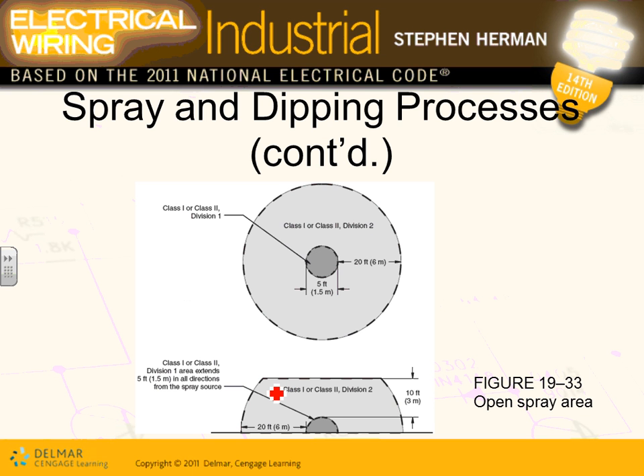So open spray areas, the same thing in the open spray areas, guys. They give you clearances of 20 feet. Look at that. That will be Class 1, Div 1, Div 2, and up to 5 feet from that opening is Class 1, Div 1. I don't know if you guys can see that right here. Could be Class 1 or Class 2 because both hazards exist. Same thing here, Class 1 and Class 2. The first 5 feet is Class 1 or 2, Div 1. The second 20 feet from it is Class 1, Class 2, Div 2. Any comments, guys, about these areas?